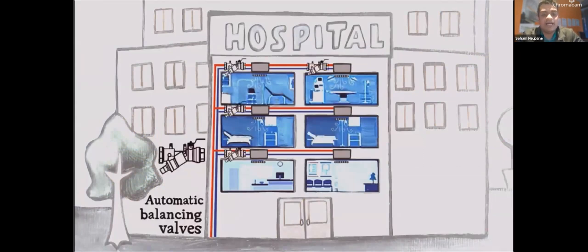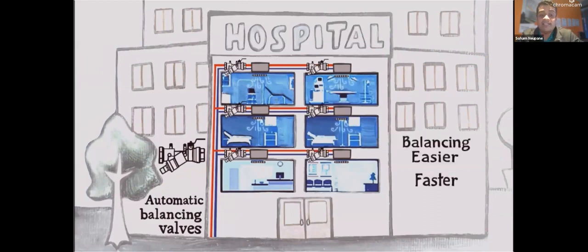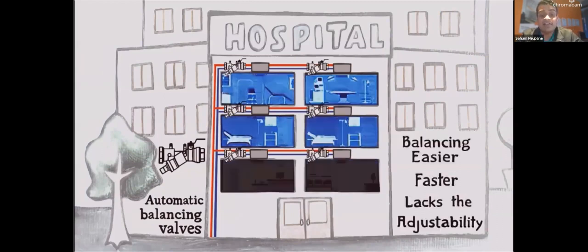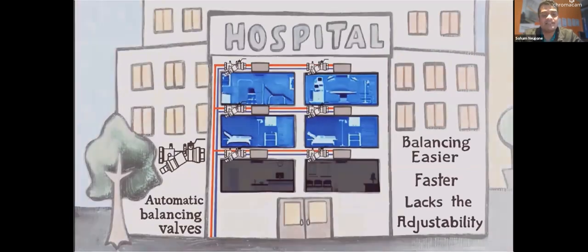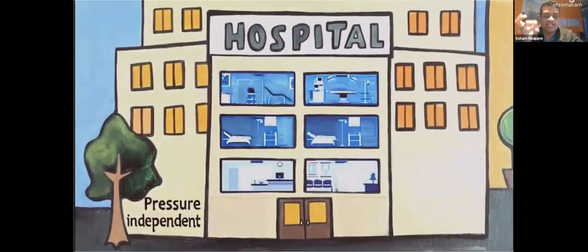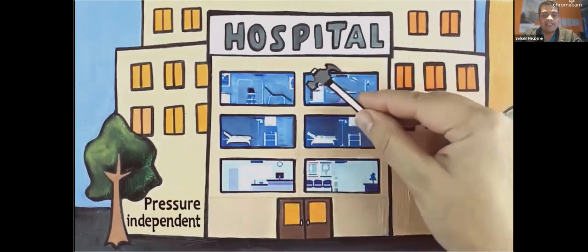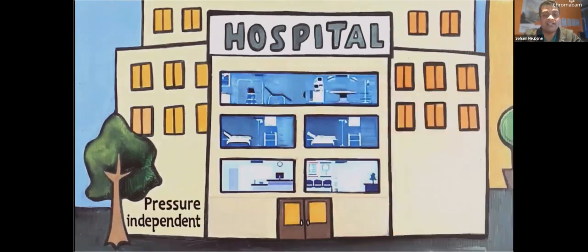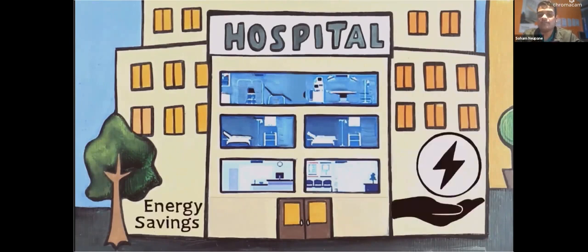The way it works is, when you have a system, you place an automatic balancing valve on each terminal unit. And it's easy, it self-balances, so it saves time, but it lacks the adjustability. In manual balancing, you could change the flow rate, whereas in automatic, you really can't. But the biggest advantage here is your pressure independence. Automatic balancing valves are pressure independent within a certain range. So that kind of takes care of that interactivity piece.